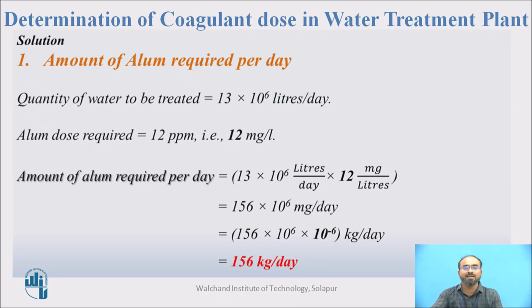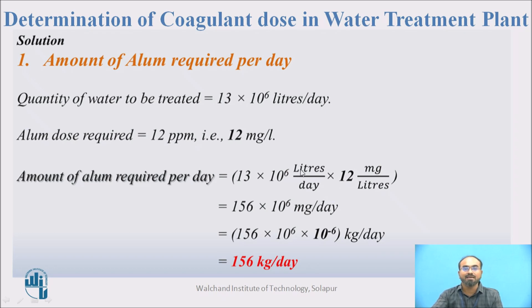First, calculate the amount of alum per day. The quantity of water is 13 × 10⁶ liters per day and the alum dose is 12 mg per liter. Multiplying flow rate by alum dose: 13 × 10⁶ L/day × 12 mg/L = 156 × 10⁶ mg/day. Converting to kg by multiplying by 10⁻⁶ gives 156 kg per day — that is the alum required.